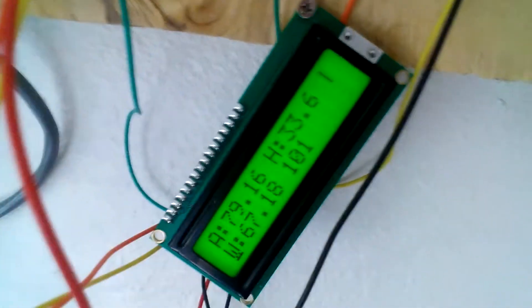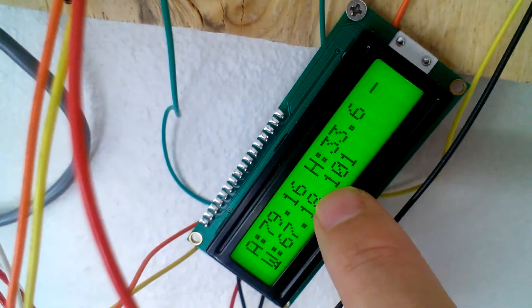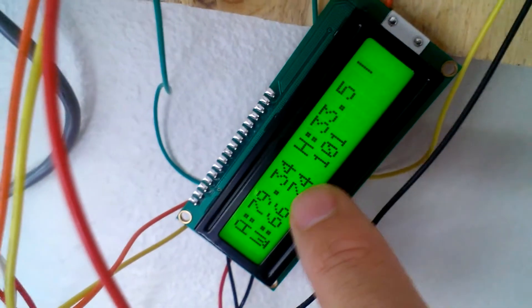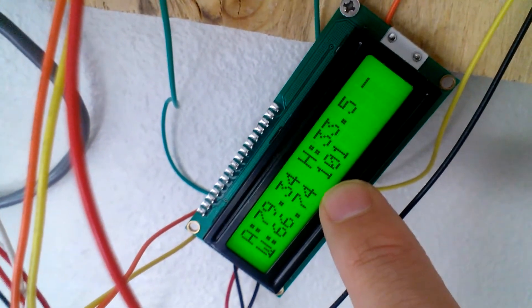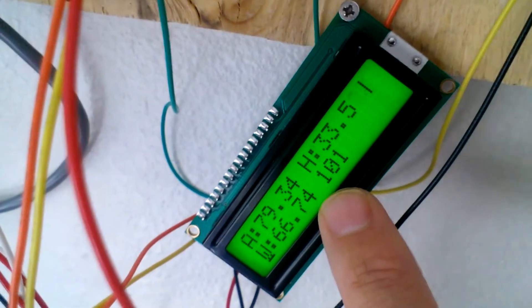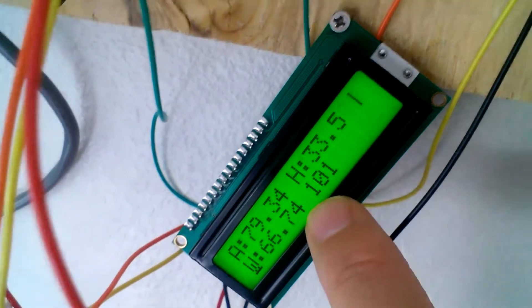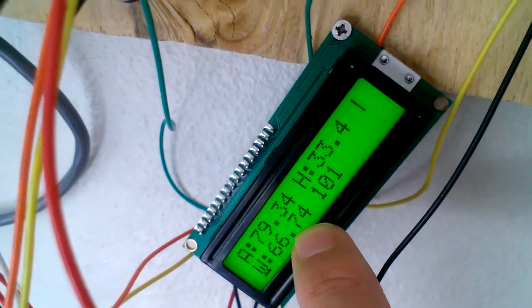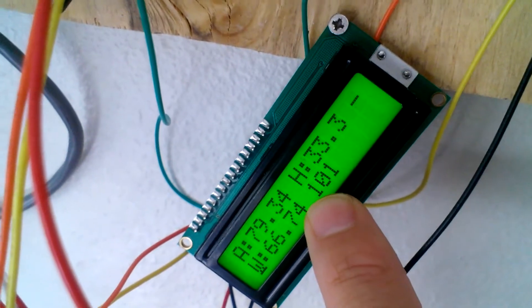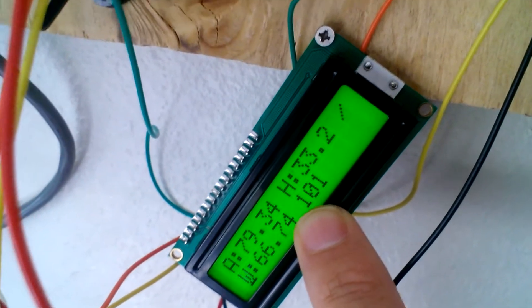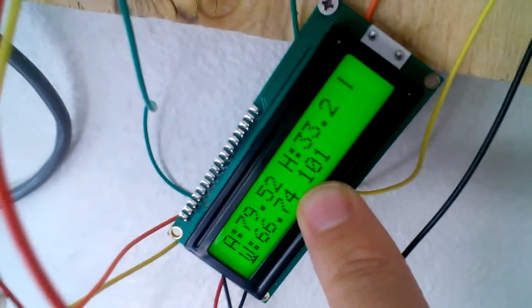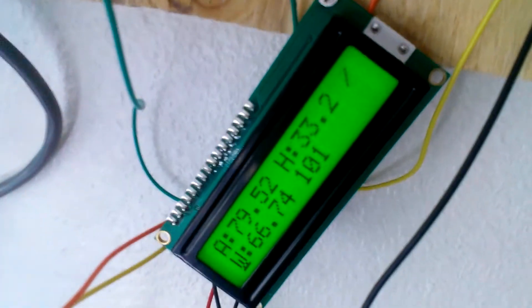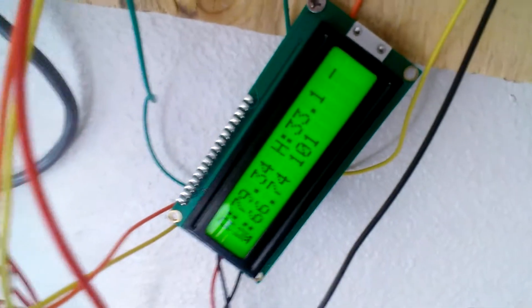As you can see, the AC fan is starting up right now. The reason why I have a delay is I let the AC fan start up and start exhausting air out of the room. If the AC fan by chance gets the temperature below its set point before the compressor turns on, it will maintain the AC fan on without turning on the compressor, and hopefully it will cool off the room before turning on the compressor. That's kind of like econo mode.